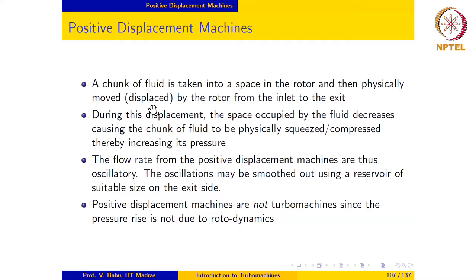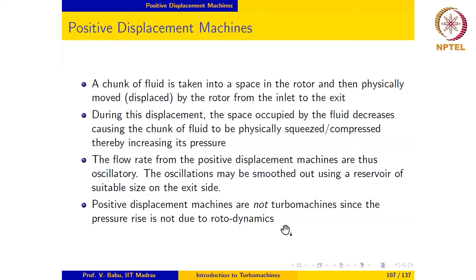Since a chunk of fluid is taken, compressed, and then sent out, the flow rate from positive displacement machines generally tends to be oscillatory, but the oscillations may be smoothed out using a reservoir of suitable size on the exit side, and that is usually done. Positive displacement machines are not turbomachines since the pressure rise of the fluid is not due to rotor dynamics but rather by physical compression of the fluid. They are widely used for pumping liquids, although designs for compressing gases are also available.